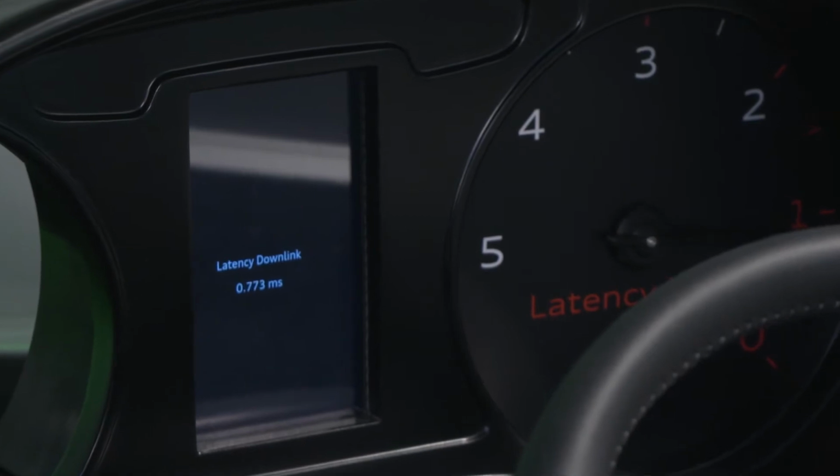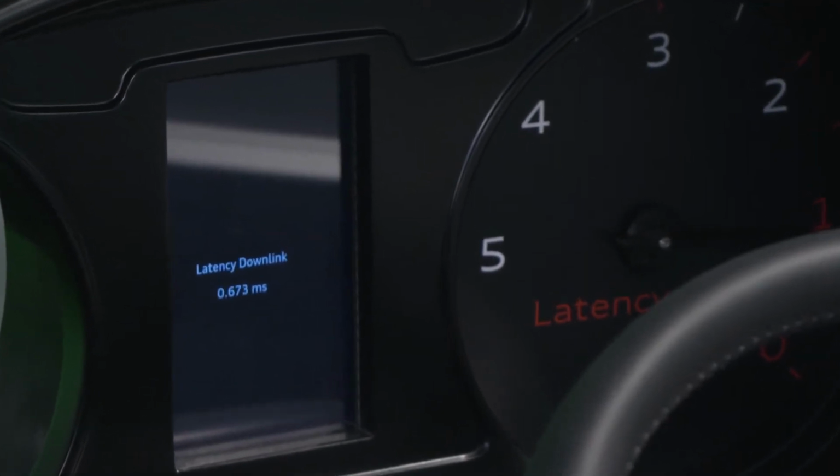This testbed uses millimeter wave 5G, and the latency round trip is about 1.2 milliseconds. We're also expecting the core to be on premises for latency and security reasons. So now the wireless emergency stop function is extremely flexible. You could have a button anywhere in the factory or even attach it to a person walking around in the factory. When these kinds of functions are wirelessly connected, it instantly creates flexibility without losing the cable's reliability and security.